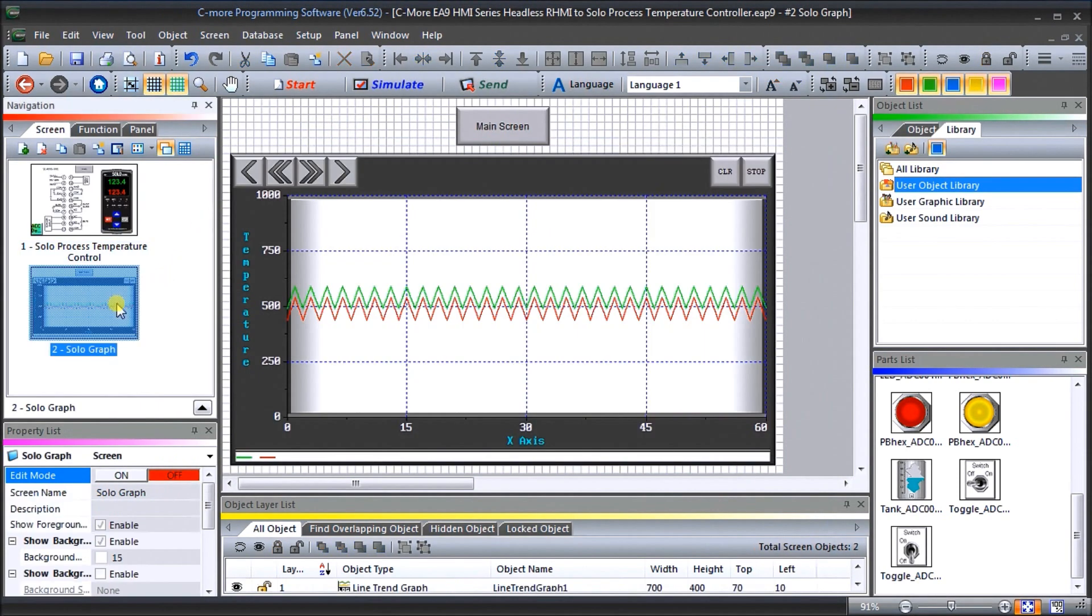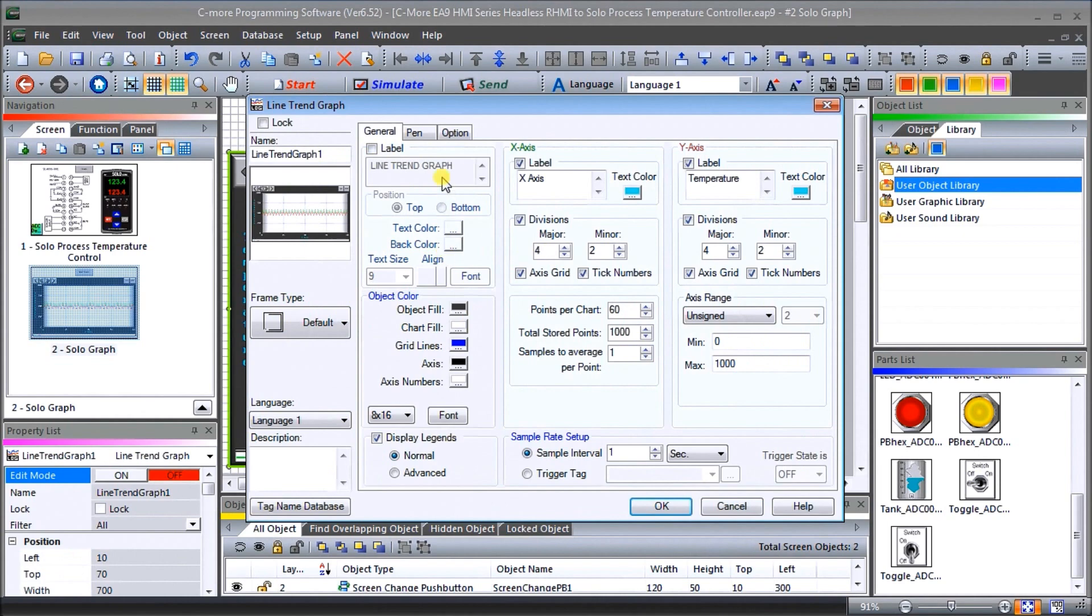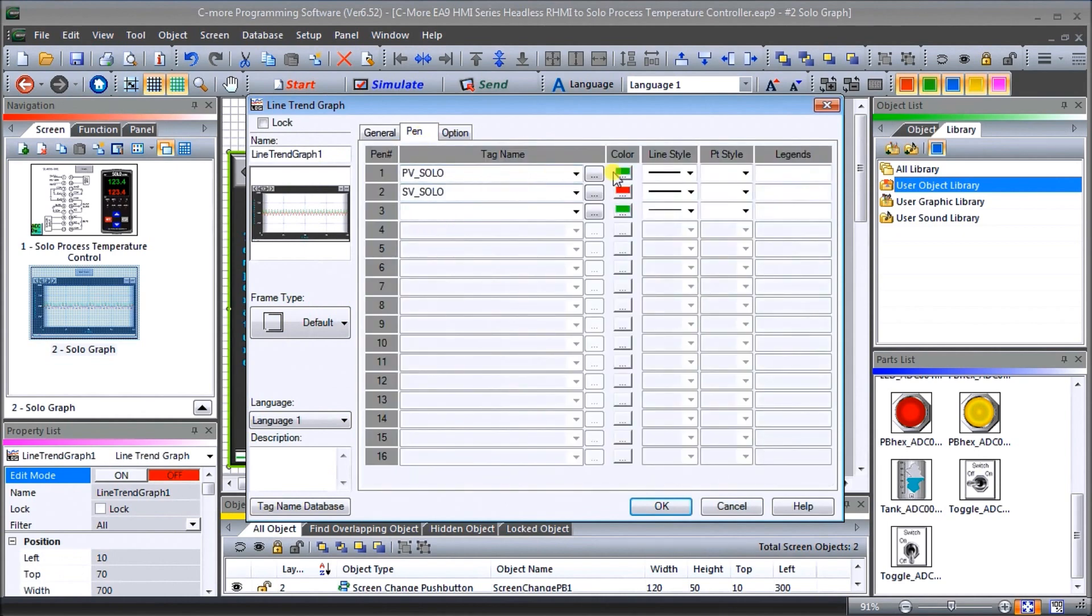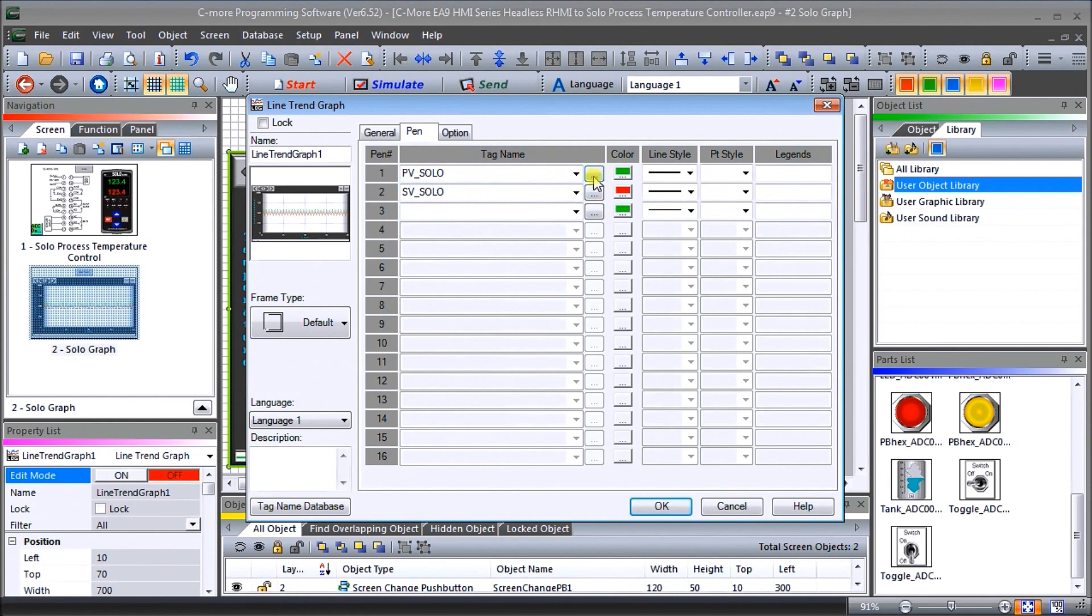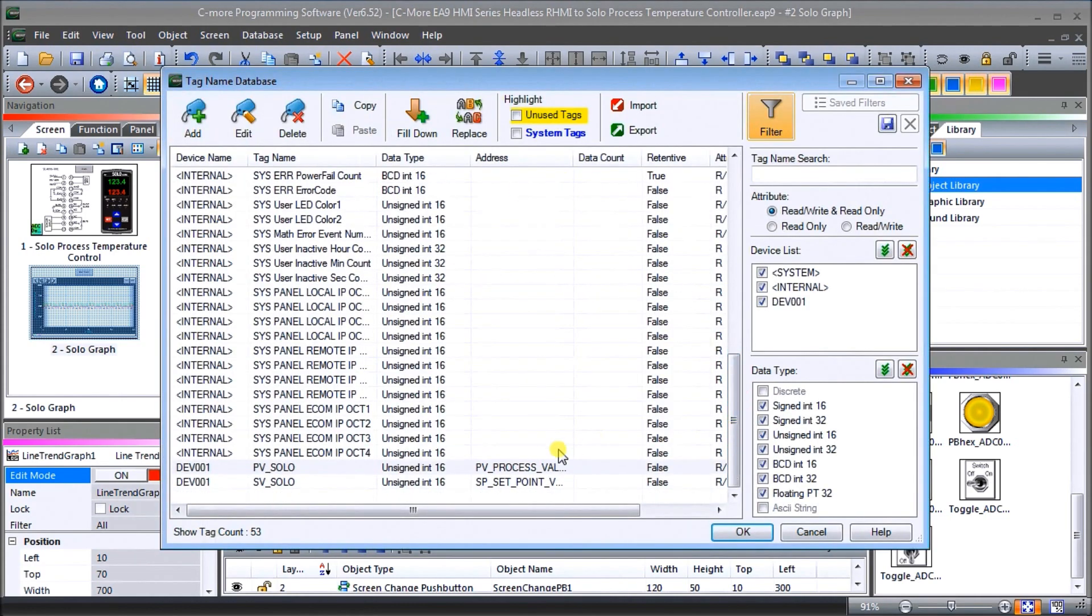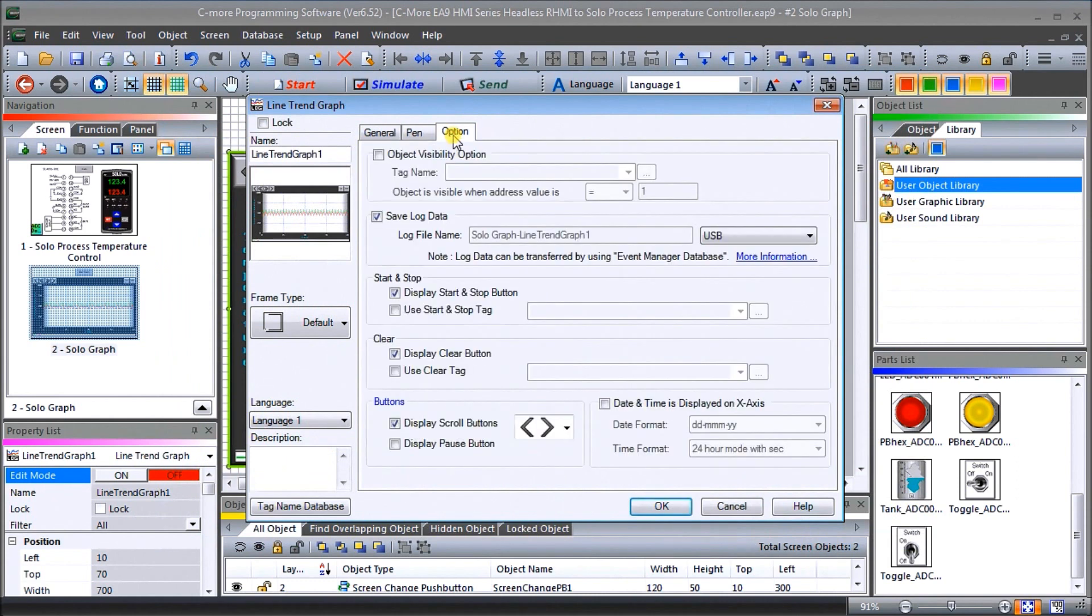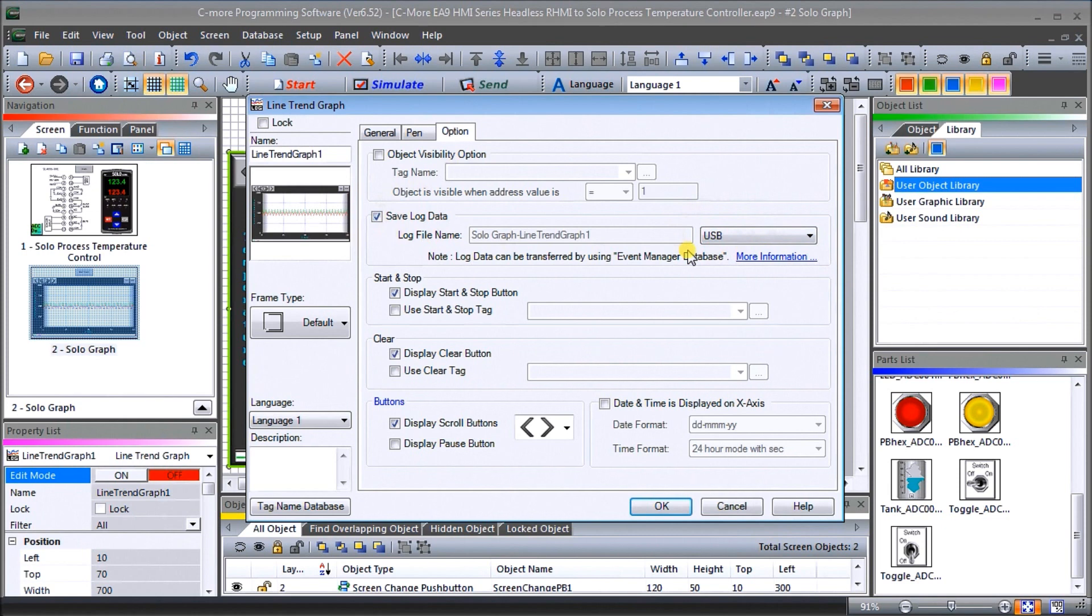And we have our solo graph. We've put our graphing on here. Our pens automatically come from our database and it's the present value and the set value of our solo in red and green that we're going to do. And it comes from our database here and you can see here's our two process that we've set up that are unsigned integer 16 bit. Then under option what we've done is we've said collect our save our log data and our log data is going to be going to a USB drive that we're going to have. So that's going to be all set up so it looks good.